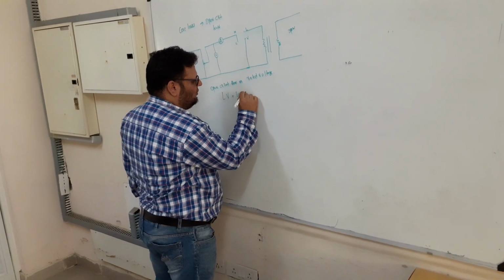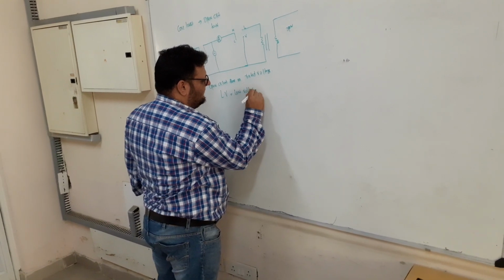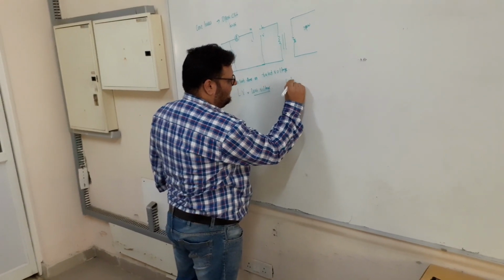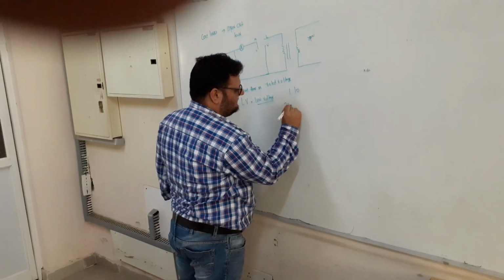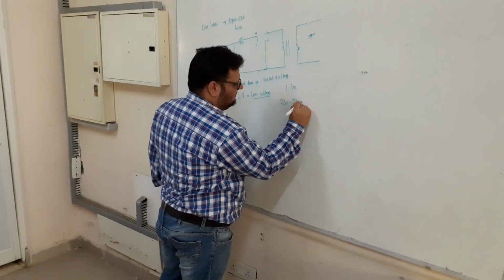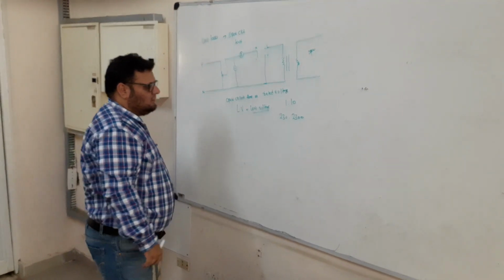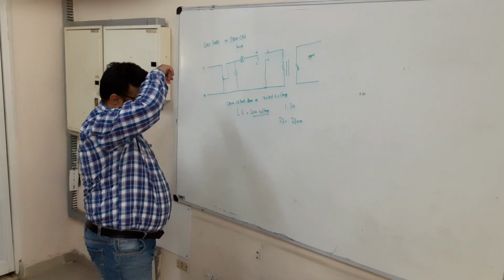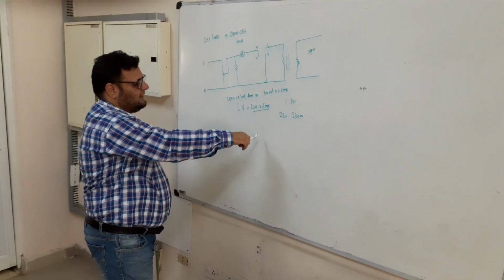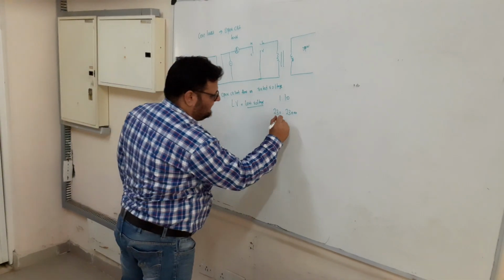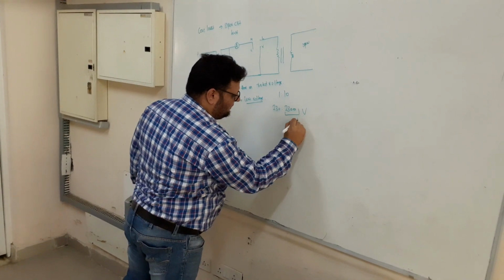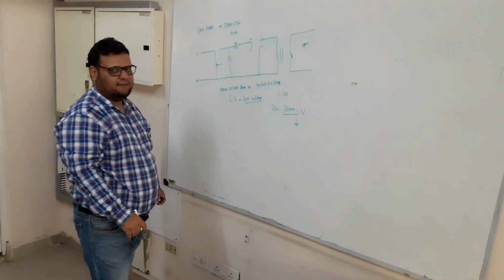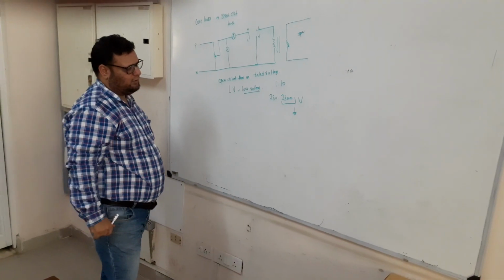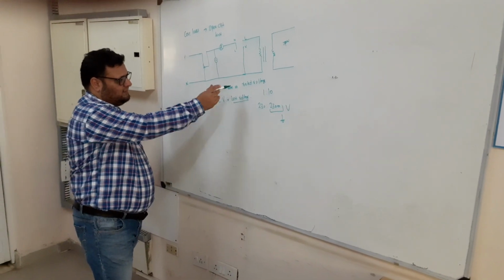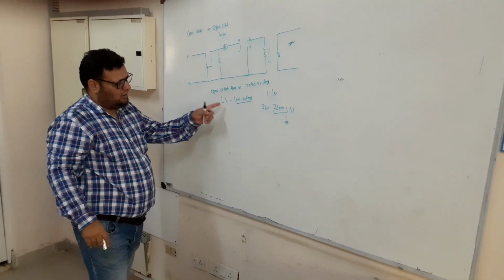Why is it carried out on the low voltage winding? Suppose you have a 1:10 transformer, so 230 on one side and 2300 on the other side. If you are not keeping the LV winding open, and you want to carry out the test on the HV winding, then you need to generate 2300 volts. Is it possible in a normal laboratory setup? It is not possible in a normal laboratory setup. Hence the open circuit test is generally done on the LV winding.